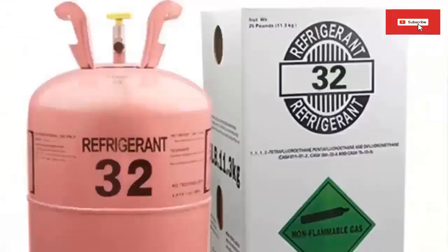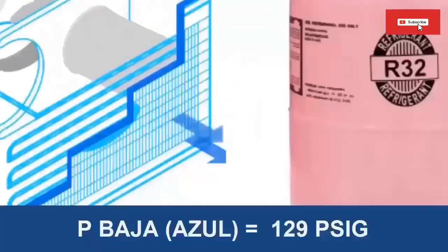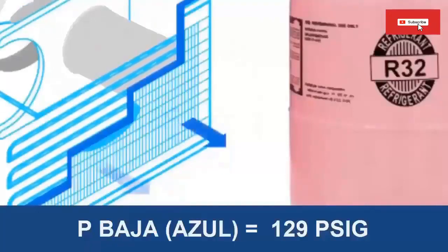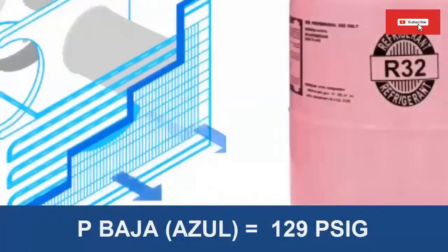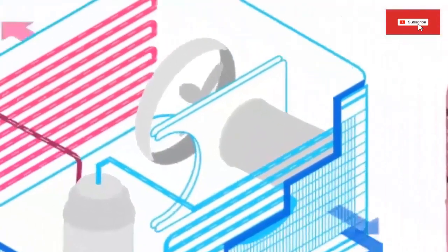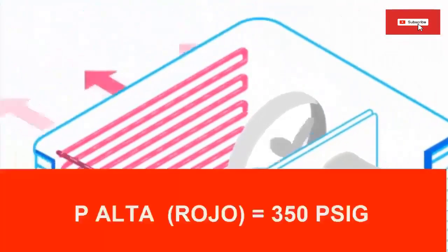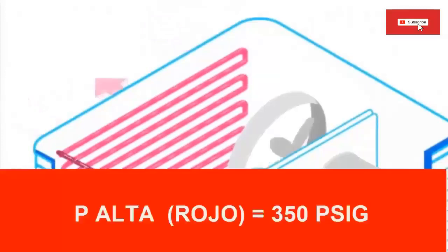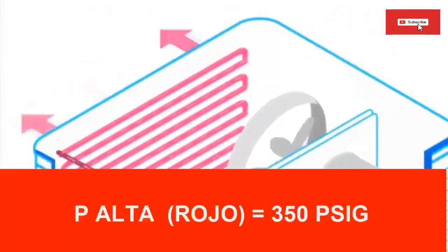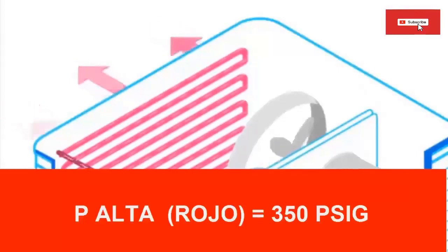For an evaporator temperature of 5°C, the pressure gauge on an R32 air conditioner should read about 129 psi. The high-side pressure of an air conditioner working with R32 for an outdoor ambient temperature of 30°C should read close to 350 psi.